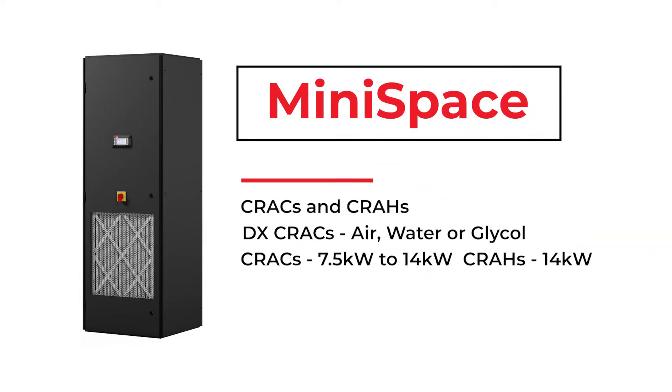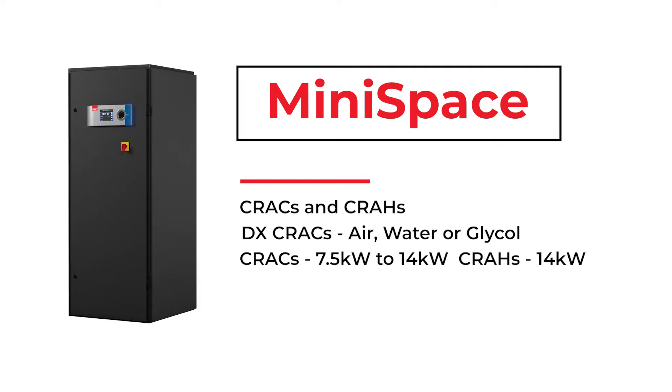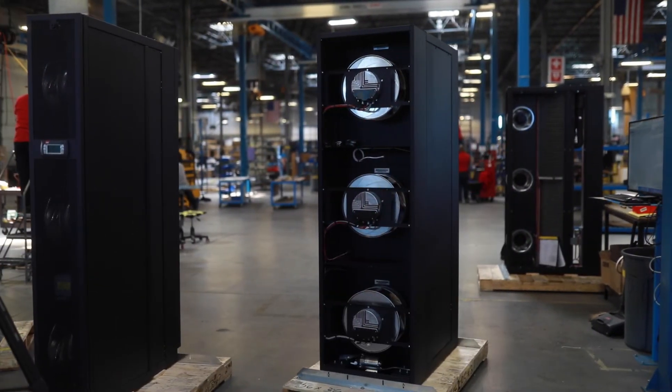The Stulz MiniSpace product offering consists of both CRACs and CRAHs. The DX CRACs are available in air, water, or glycol cooled models with a capacity range from 7.5 to 14 kW. The CRAHs have a capacity of 14 kW and can be turned downward for air and water flow rates for lower capacity needs. Both CRACs and CRAHs are available in our smallest vertical unit footprint of approximately two square feet.